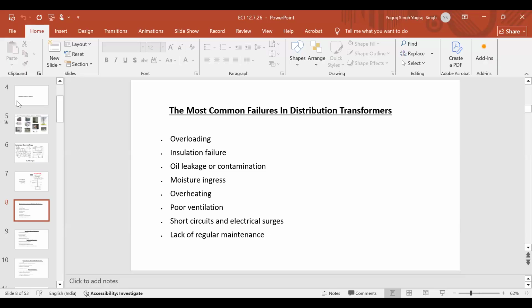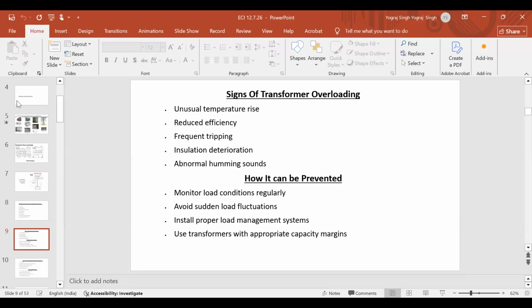Now, how will you judge that my transformer is getting overloaded? Unusual temperature rise, reduced efficiency, frequent tripping, insulation deterioration, abnormal humming sound. These things are telltale signs you will see, and you will find these are the problems. My transformer is getting degraded. Now, what should you do? You should monitor your load regularly and avoid sudden load fluctuations.